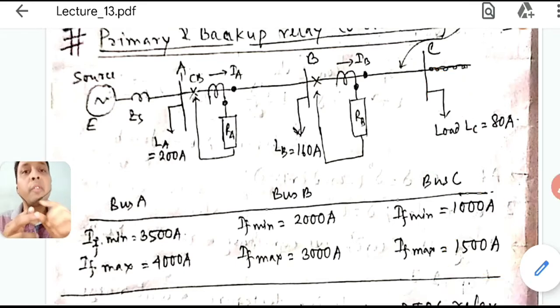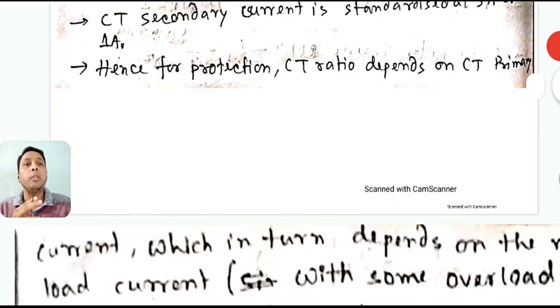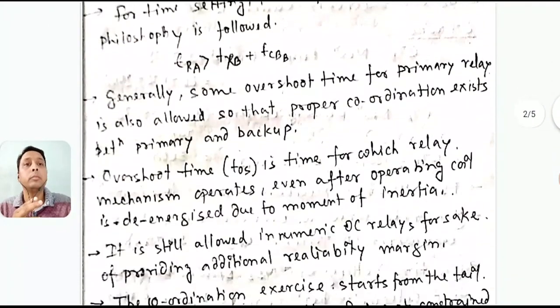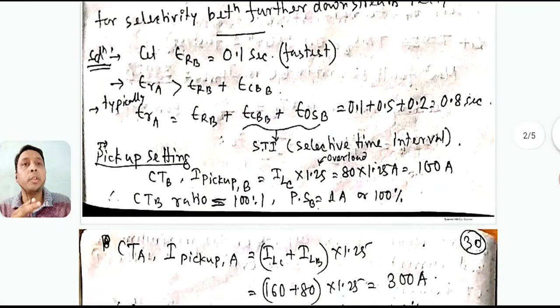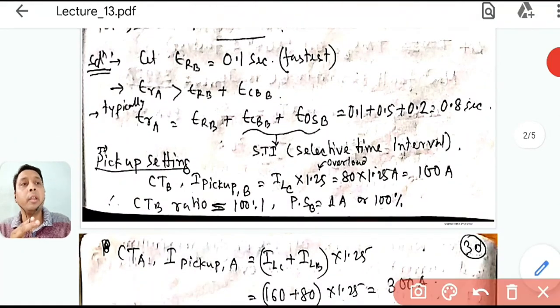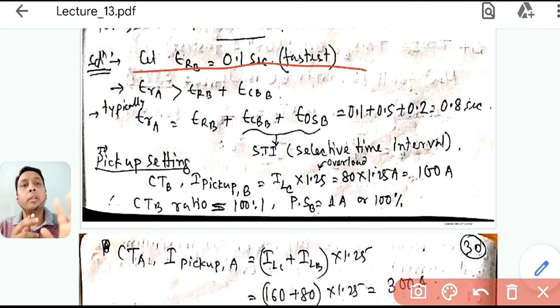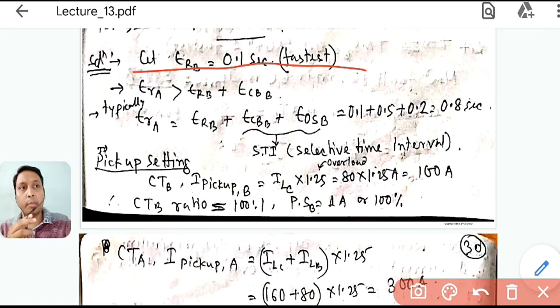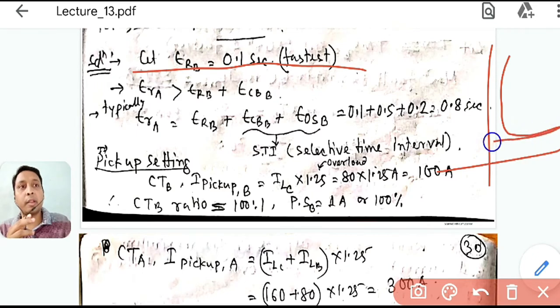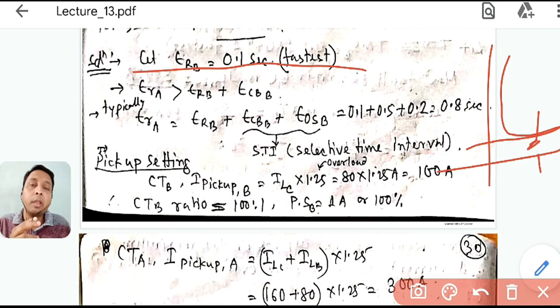We start the DTOC solution from the tail end, which is relay B. Since relay B is in our control, we make it as fast as possible — 0.1 second. For a DTOC relay, the operating time does not depend on current; the curve is flat, so the time is fixed regardless of fault current magnitude.